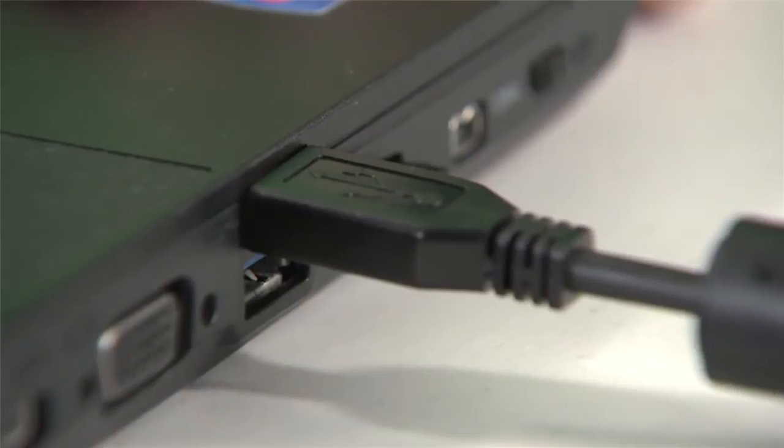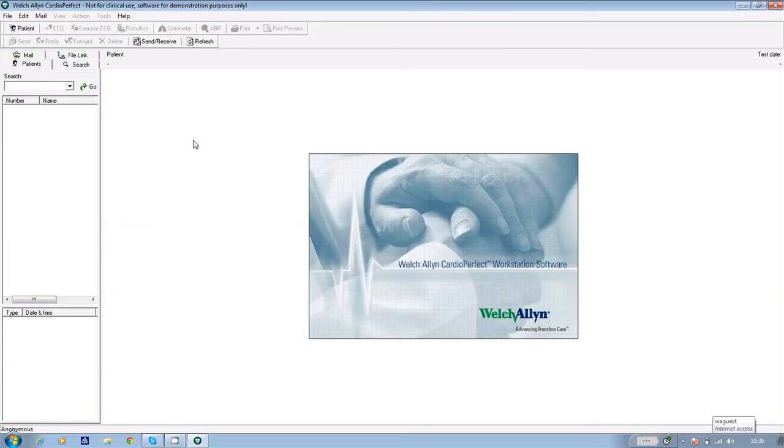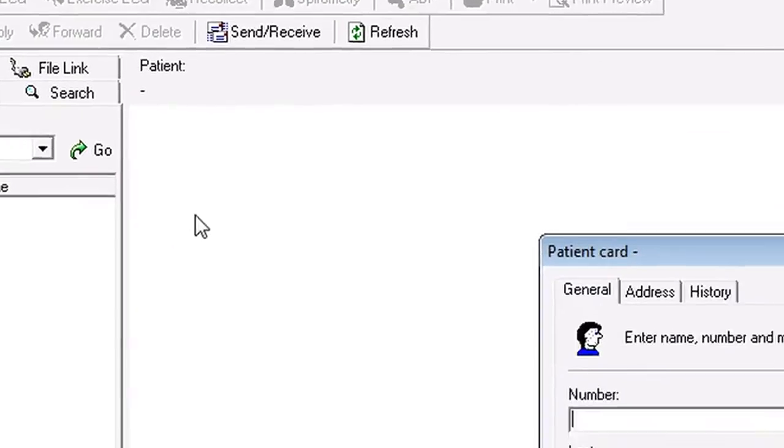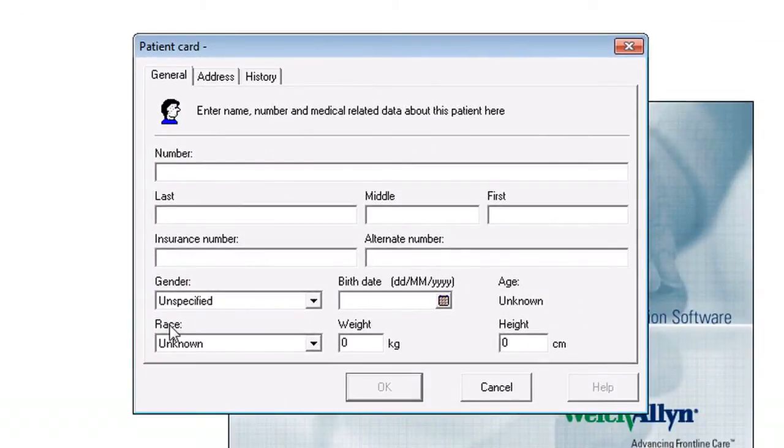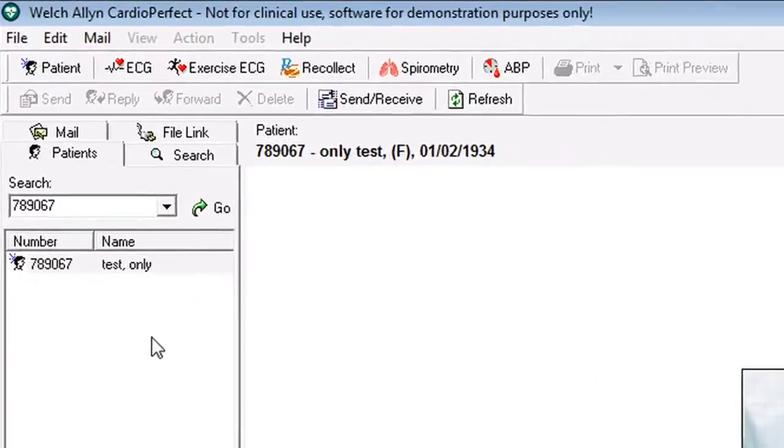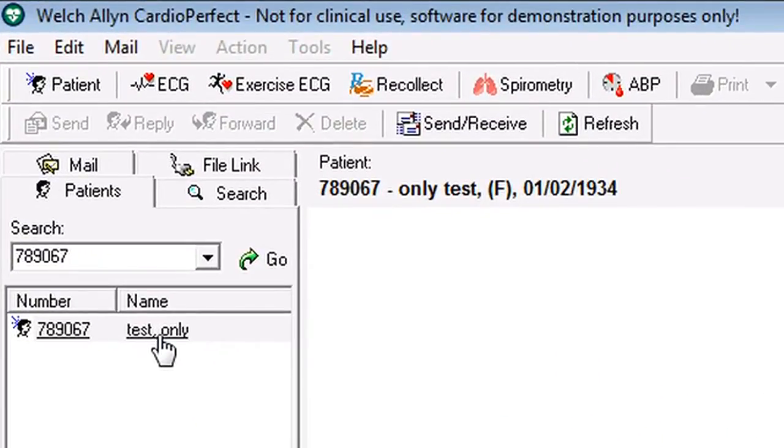Now connect the USB cable to your PC and go into the Cardio Perfect software. Double click on the icon. And if the patient hasn't had an ECG before, click on patient in the top left hand corner of the screen. When the patient record card appears, fill in the patient ID number, NHS or other, the last name, the first name, the gender, and the birth date. And then click OK. Their details go into the memory and they'll be there next time the patient comes in for another test.